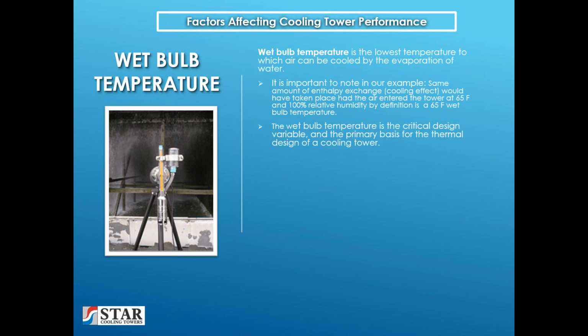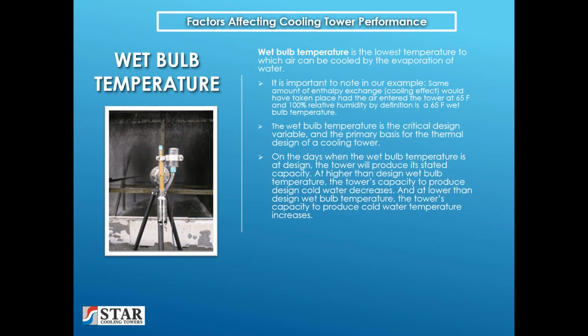The wet bulb temperature is the critical design variable and the primary basis for the thermal design of a cooling tower. On the days when the wet bulb temperature is at design, the tower will produce its stated capacity. At higher than design wet bulb temperature, the tower's capacity to produce this design cold water temperature decreases. And at lower than design wet bulb temperatures, the tower's capacity to produce cold water temperature increases.